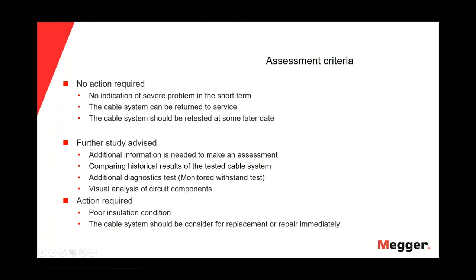The next one is further study advised, which means that additional information is needed to make an assessment. Maybe we can compare historical results of the tested cable system, or we can do additional diagnostic tests, for instance, a monitored withstand test. Or maybe we can do an inspection, a visual analysis of the circuit components, to look for splices with water or wet terminations, okay? And action required, the last result we can get, means that we have a really poor insulation condition and the cable system should be considered for replacement or repair immediately, okay?